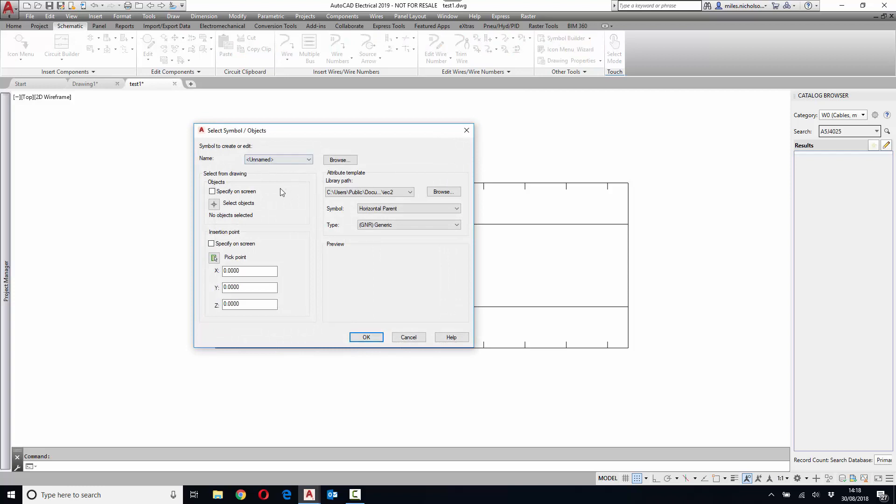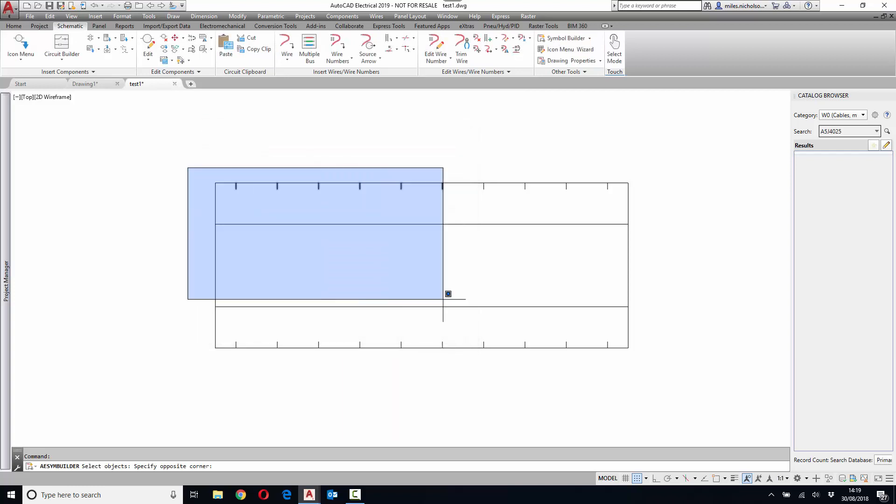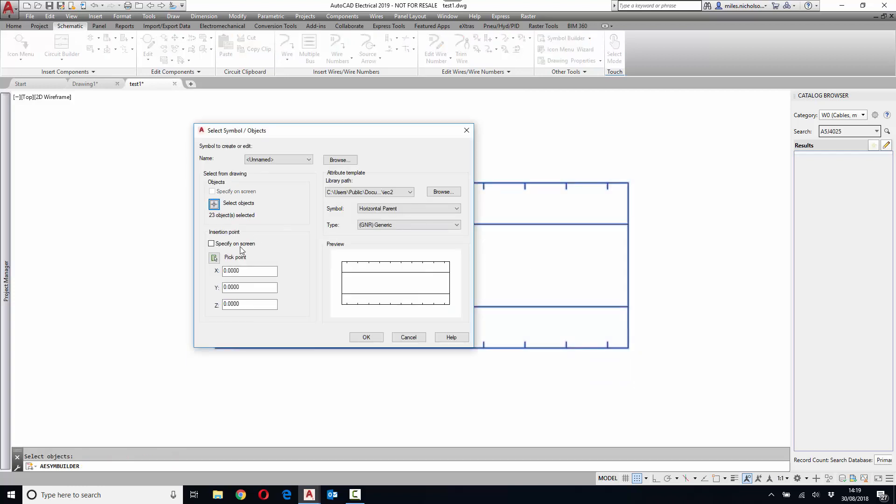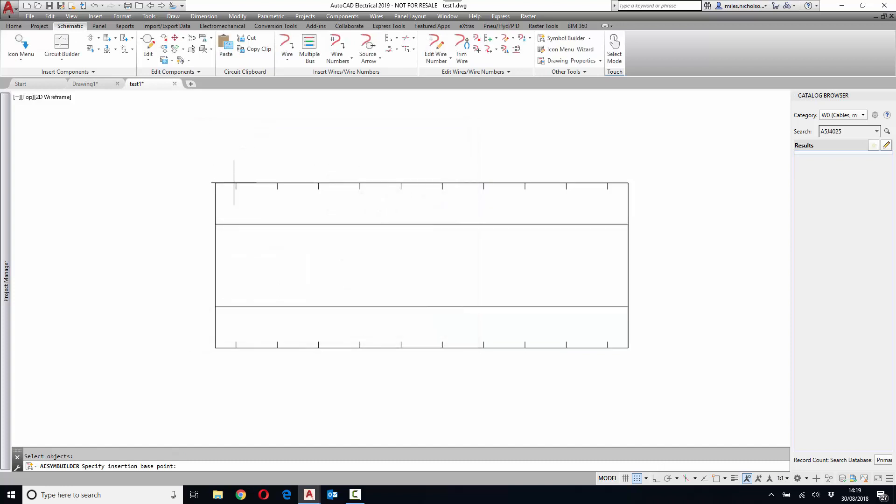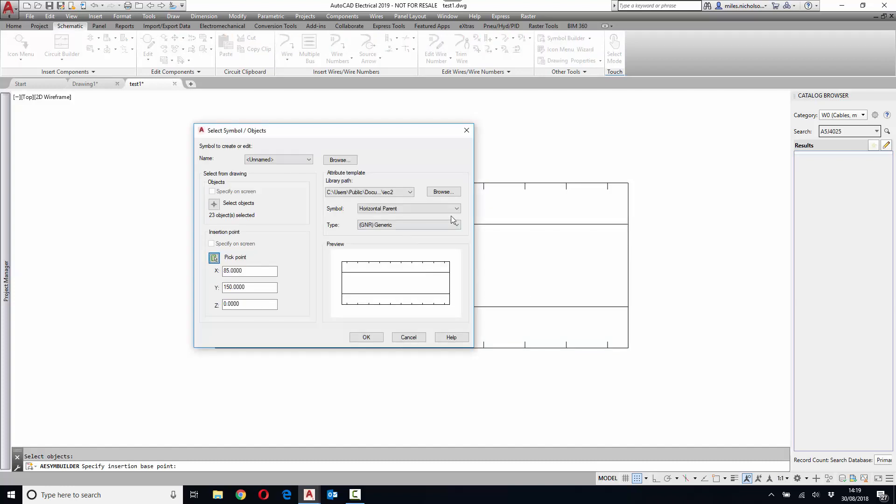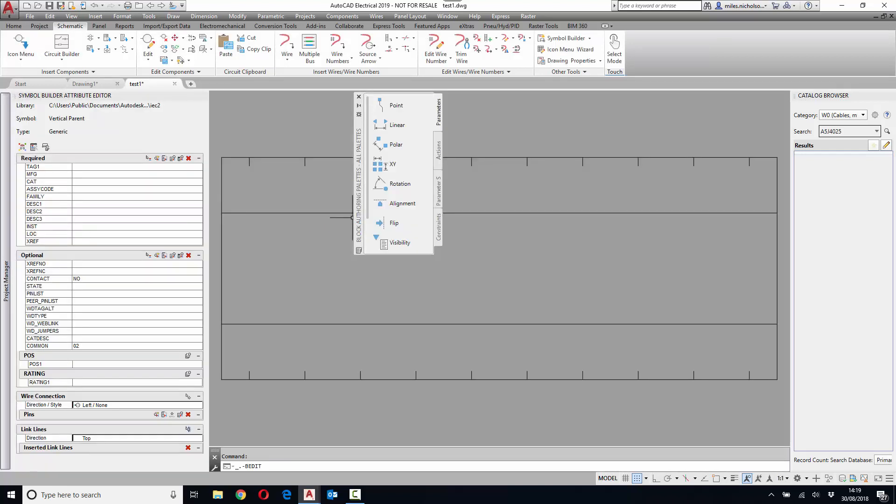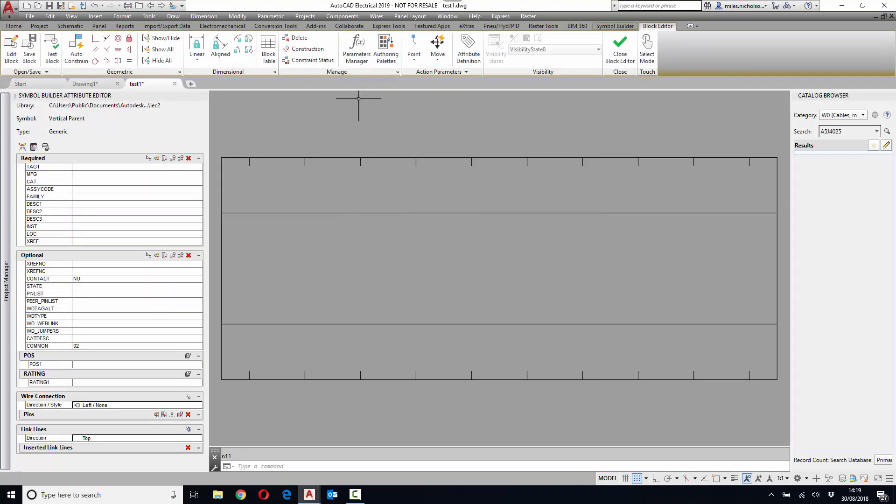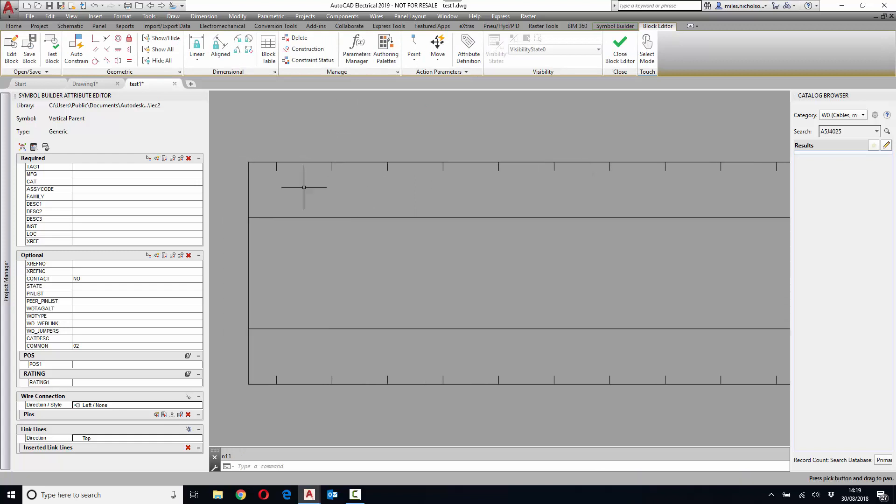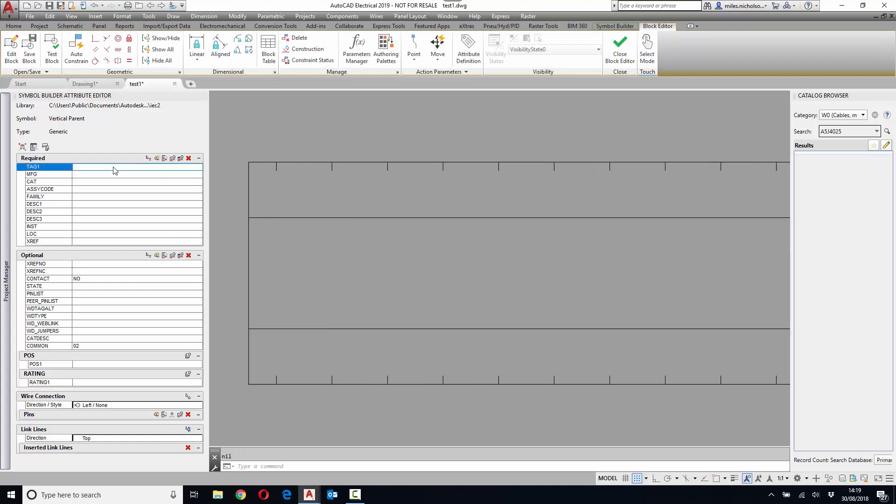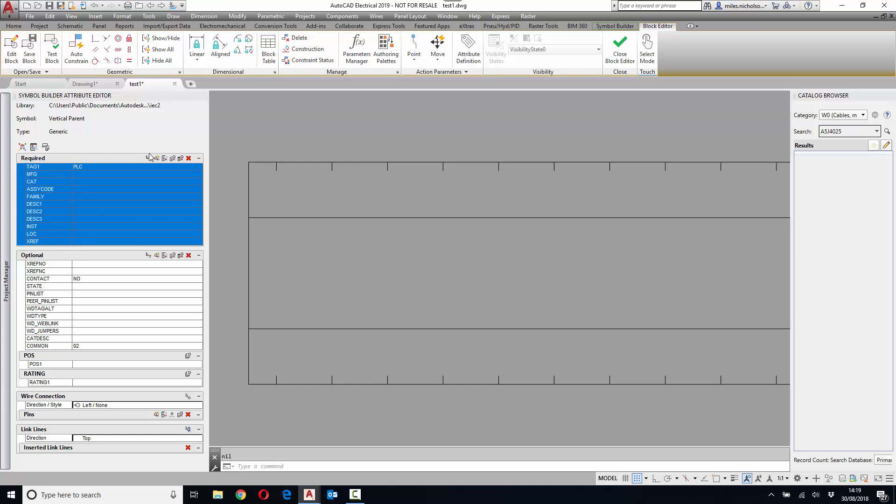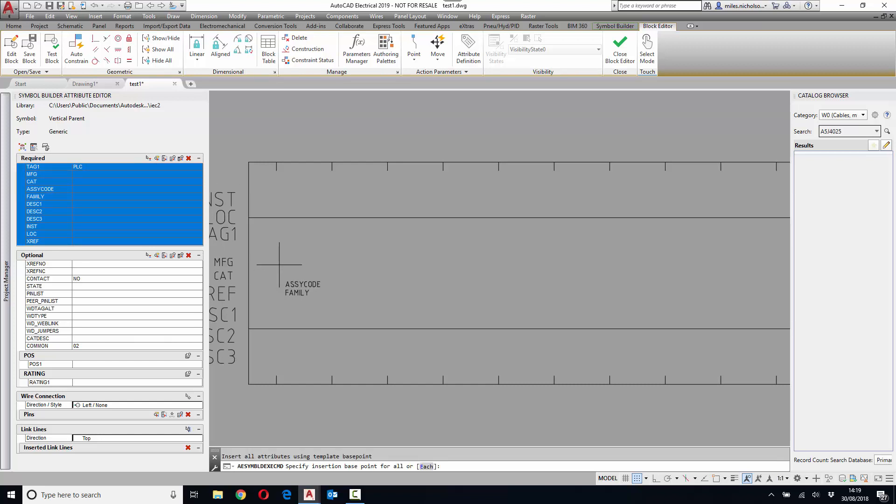Select symbol builder, select your objects that represent the PLC, define a base point. As the connections of this device coming in vertically, it's a vertical parent. We can define the tag as PLC and insert all of the required attributes very quickly.